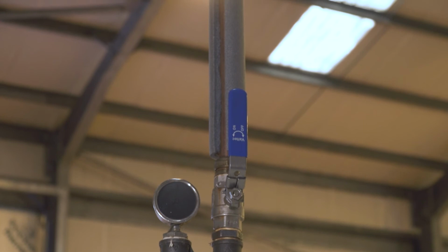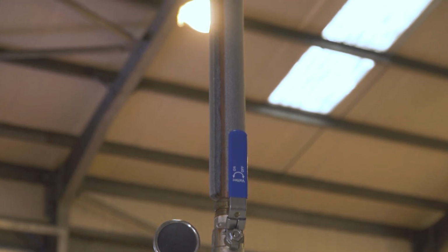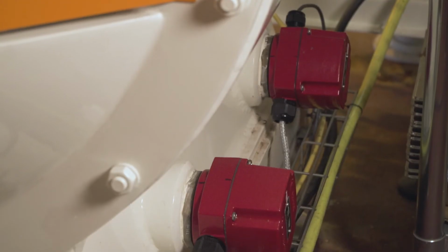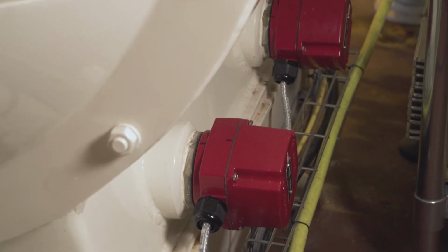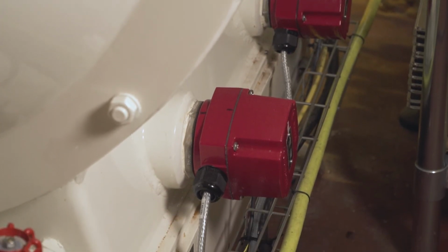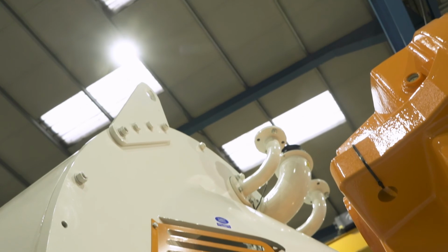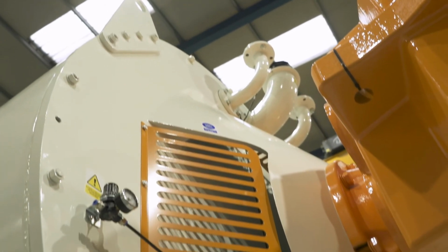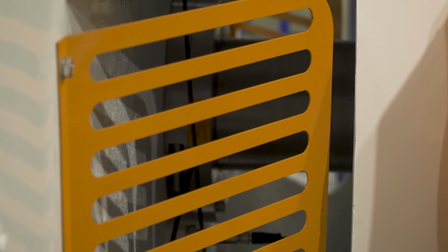Check the water level in your chiller system at least every week. Remember to ensure that the sump area is filled with water before activating the heating. Finally, a compressed air supply of 0.5 bar should be fed to the cinch seal. This will ensure there is no product seepage from the gearbox end.